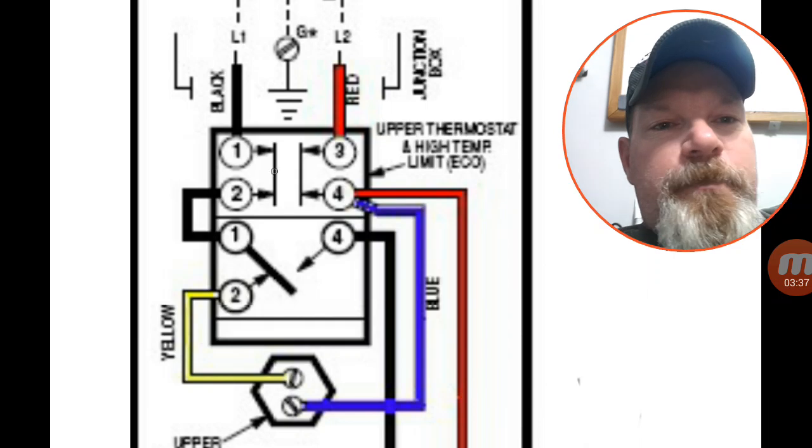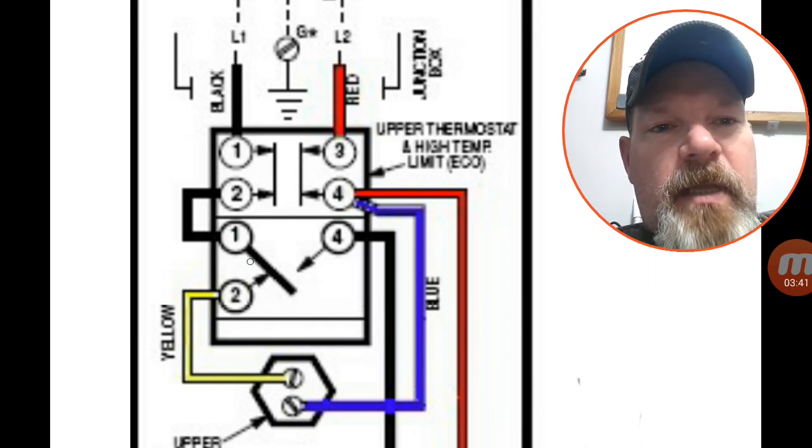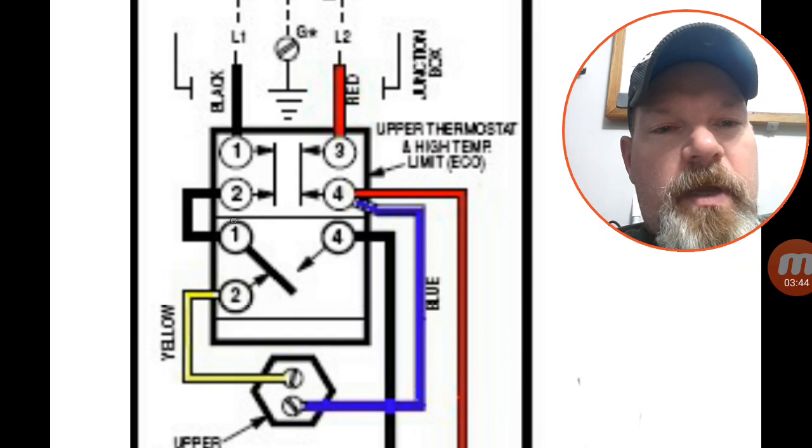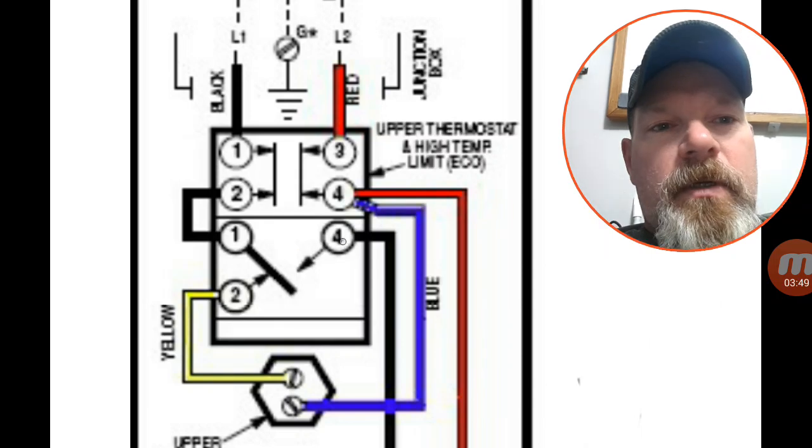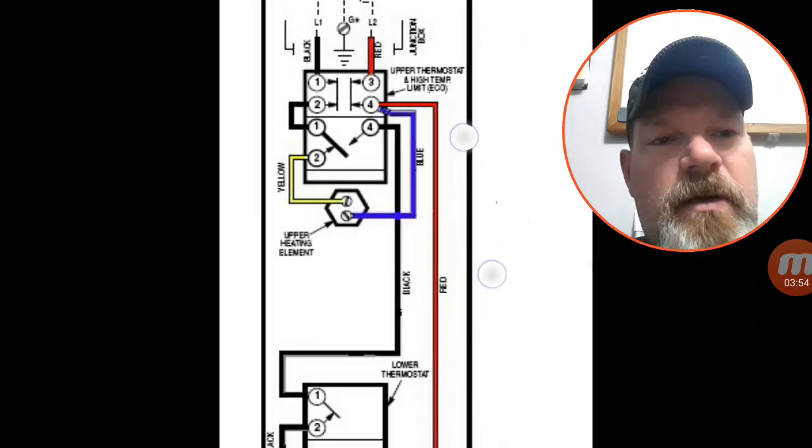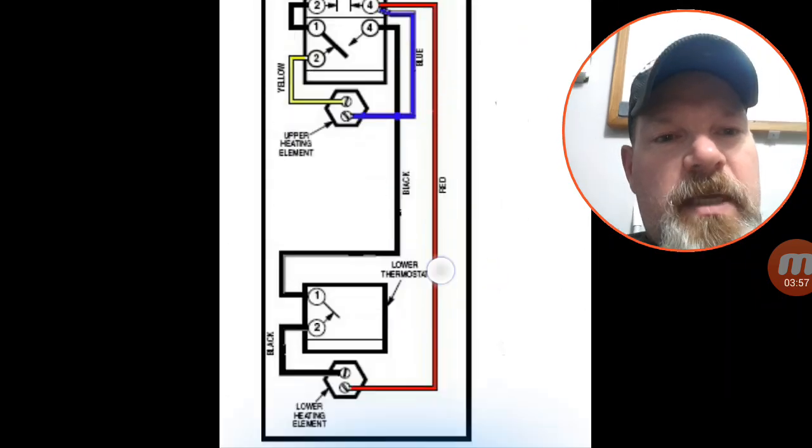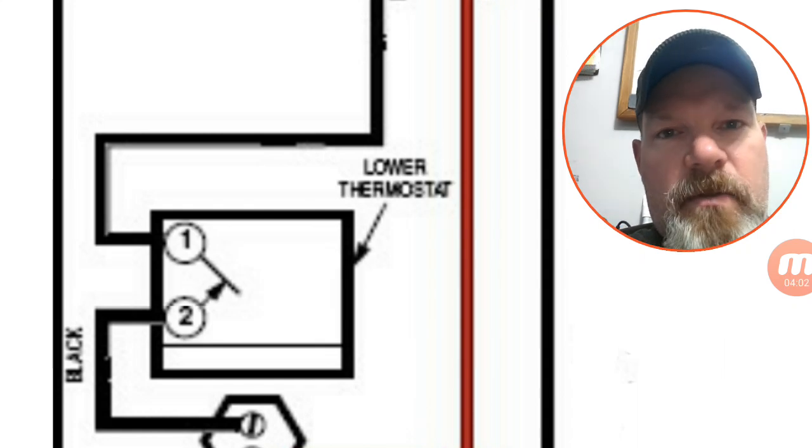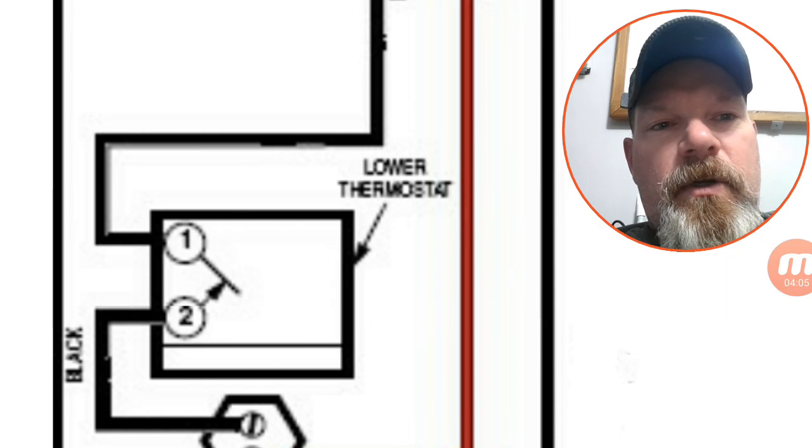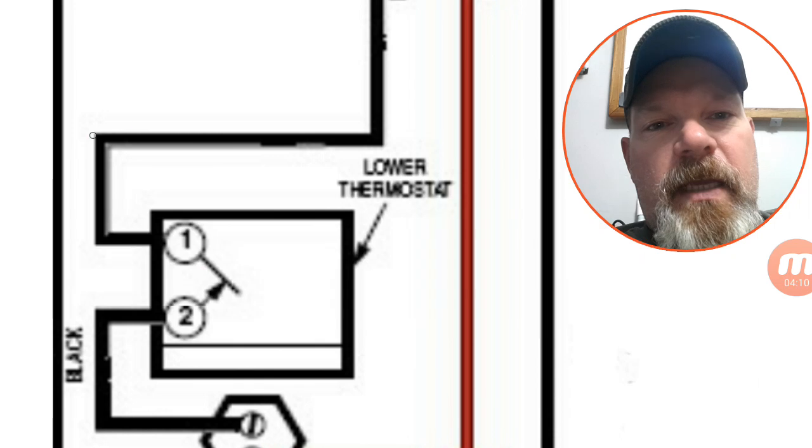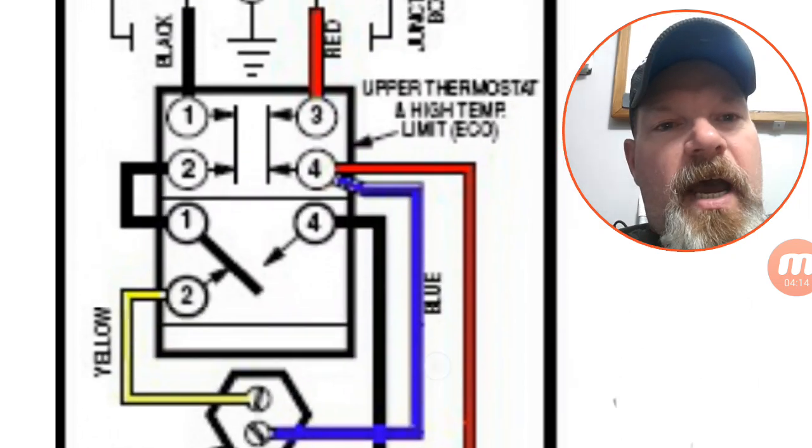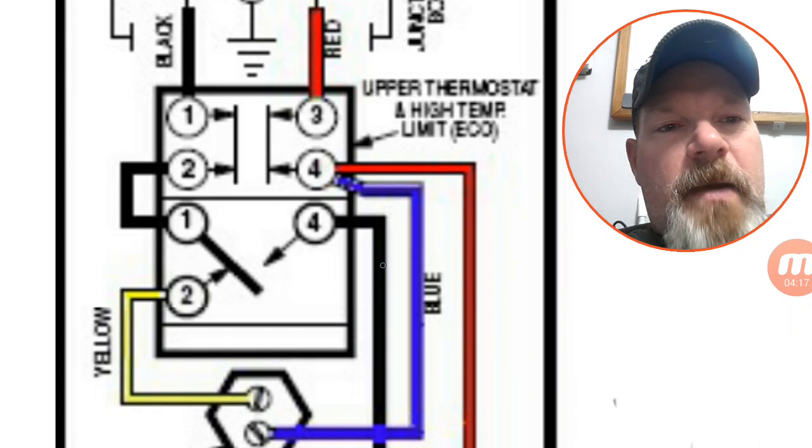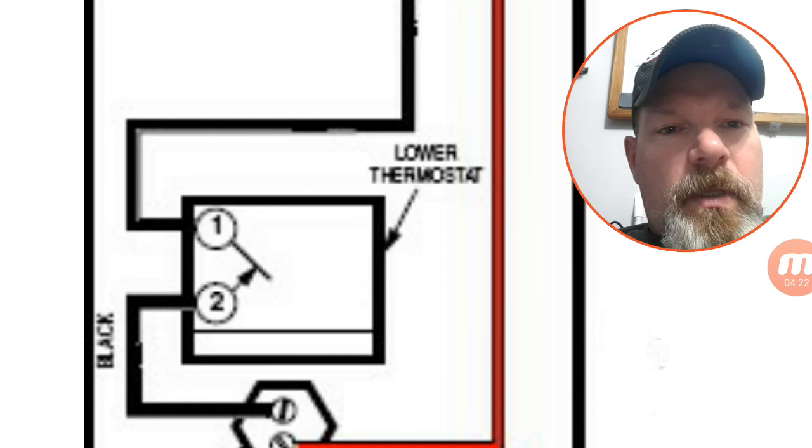To follow the wiring down, it's on the common leg of the single pole double throw switch, so it's either going to send power to the upper element or it's going to send power to number four, which if we trace that down here comes in at the top of that thermostat. Under normal conditions this thermostat is not calling for any heat, so when the water heater is totally satisfied, the top thermostat is sending power down number four and then it's just sitting here waiting for something to happen.